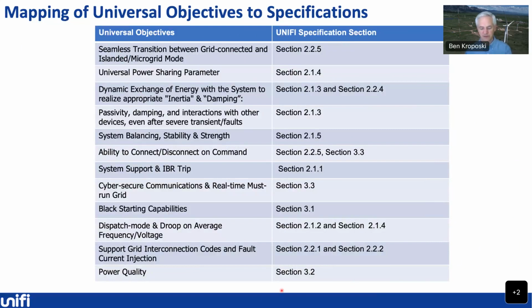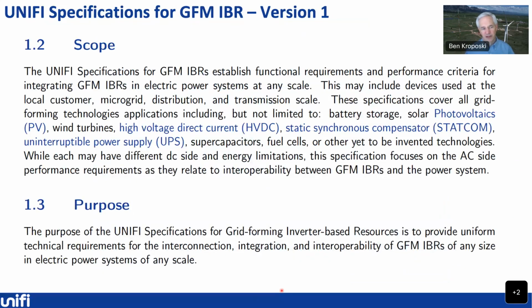I won't go into this in too much detail, but I'll start walking through the document at a high level to give you an idea of what's inside this particular document and how we're using these specifications. So first thing is the scope. We want to make sure that this is inclusive of any grid forming inverter-based resources that connect to larger scale systems. So this should be able to be used for microgrids, distribution level, transmission scale equipment, and covers a full range of grid forming technologies, whether it's PV inverters, wind turbine inverters, even HVDC. These things all have some device in there that could potentially be a grid forming technology. And the purpose is to provide these uniform specifications so that you can integrate these easily into the systems.